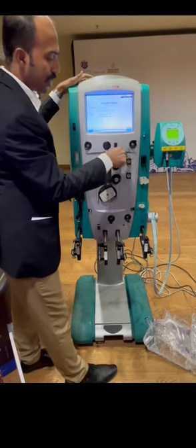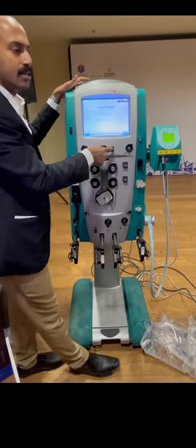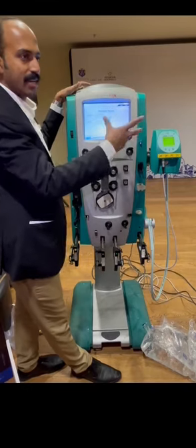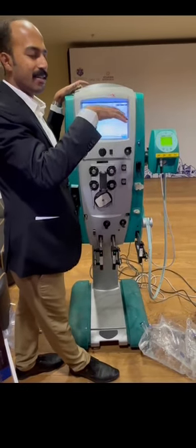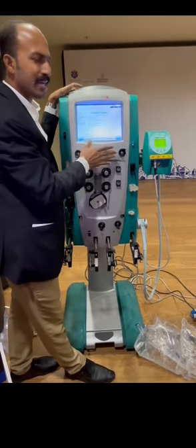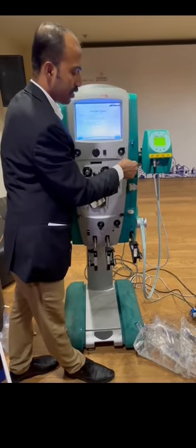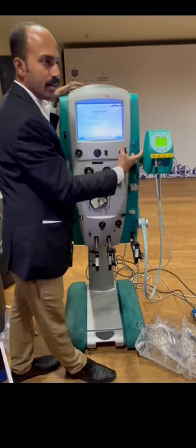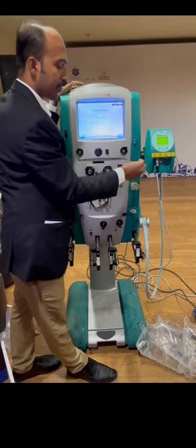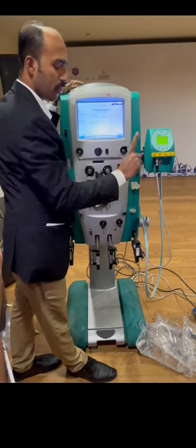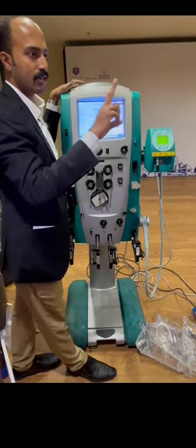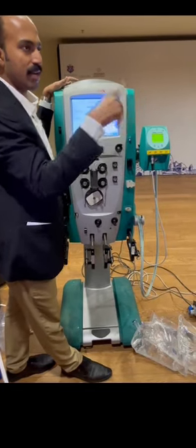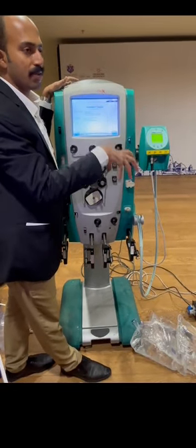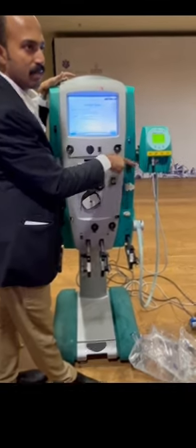Okay, then this is a discharge ring, to avoid static electricity, to avoid any ECG variations and all. Okay, like earthing. Then we have that deaeration chamber holder. Okay, then here we will keep the deaeration chamber. We have only one deaeration chamber. In HD there are 2, before the filter as well as after the filter. To minimize the blood volume, we kept only one deaeration chamber in the circuit.